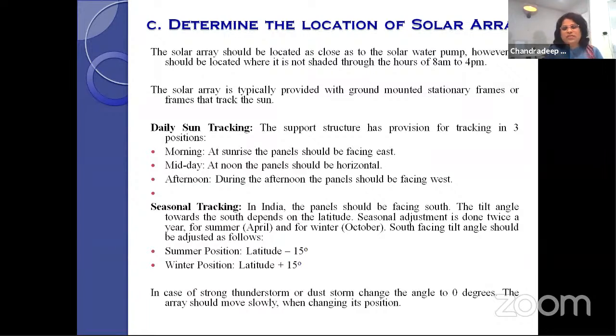Sometimes you find fixed systems instead. Tracking is seen less often because the investment cost is high, and we don't encourage much tracking since it involves a huge weight. The mounting structure holds the weight of the solar modules - one mounting structure holds more than 1200 watt peak, meaning 4 modules of 300 watts each. If you allow such a heavy mounting structure to move daily, there's a chance of breakage and collapse of the whole structure. So if going for tracking, it's better to use one module per mounting structure to reduce weight. But with many modules, tracking increases the chance of breakage - so it's better to go for a fixed system if the radiation is good.